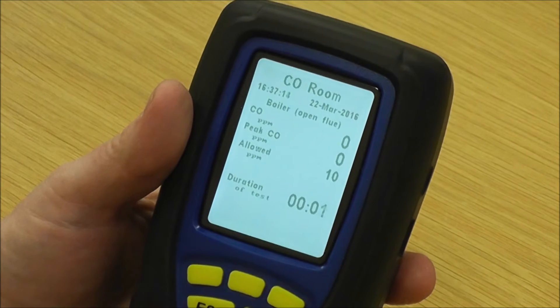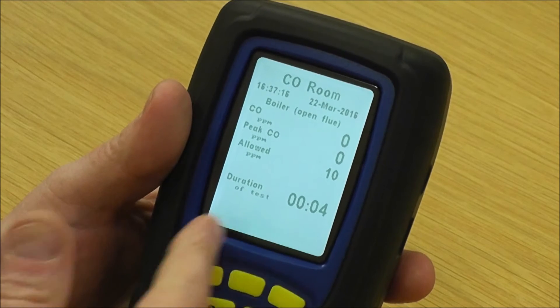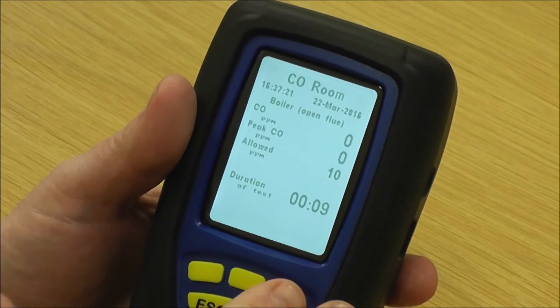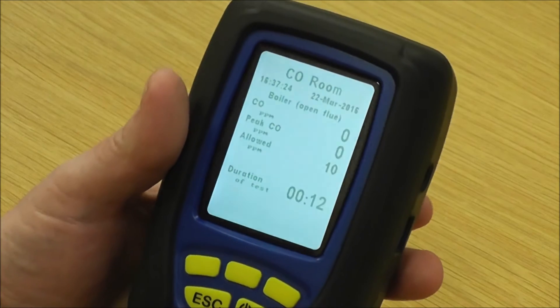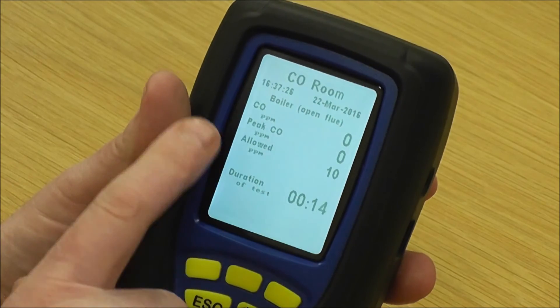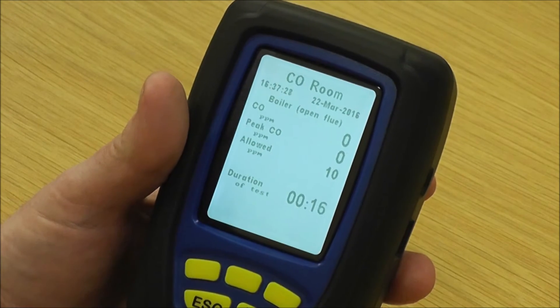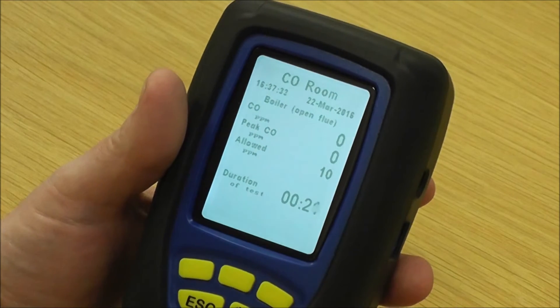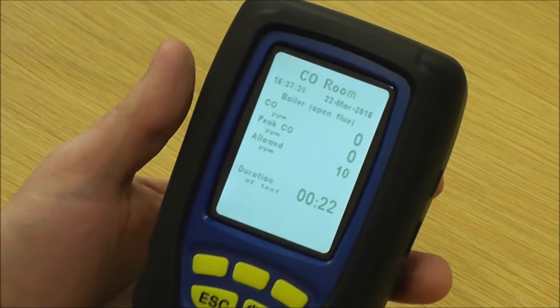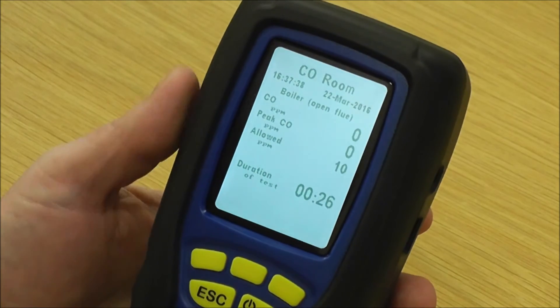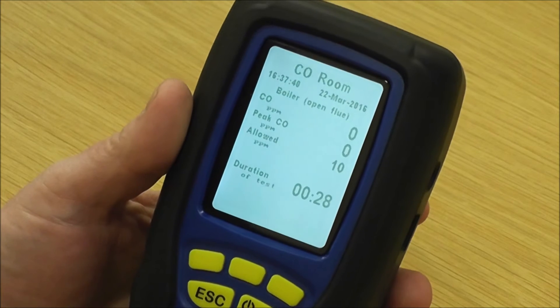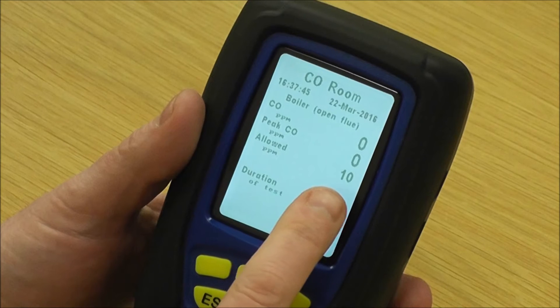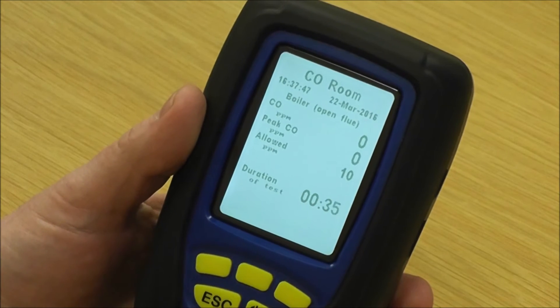That would start the duration. You'll notice there's no stop key and no print key. The reason for that is it's got to meet the minimum duration, which on this particular test is 15 minutes. After it's met the minimum duration, you'll be able to look at the details and make an informed decision on whether it's a flying pass and 15 minutes is enough, or whether you need to let it run for the second duration, which is doubling up the test to 30 minutes. You'd do that if you'd exceeded the 10 ppm or got extremely close to it.